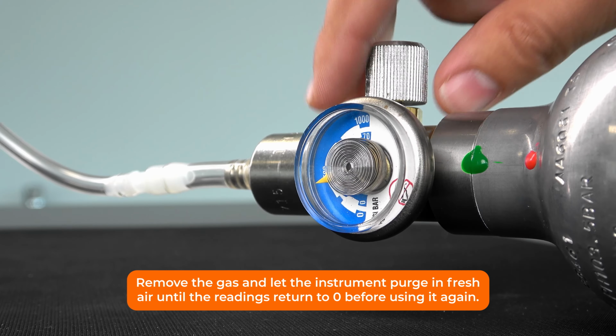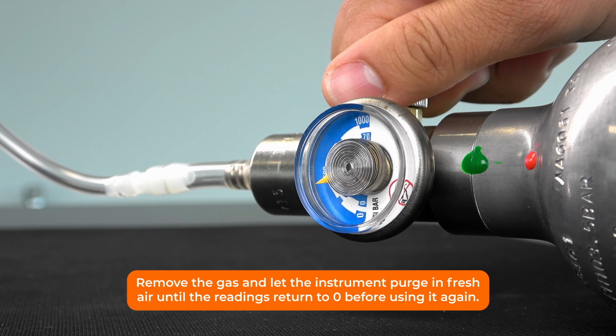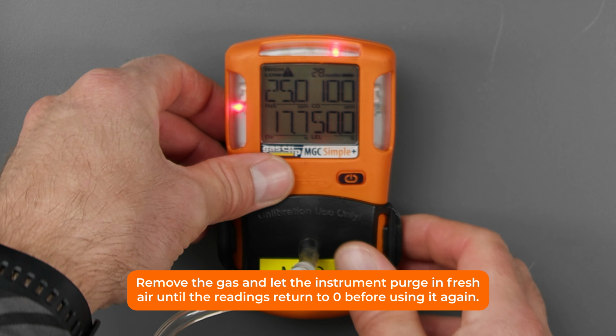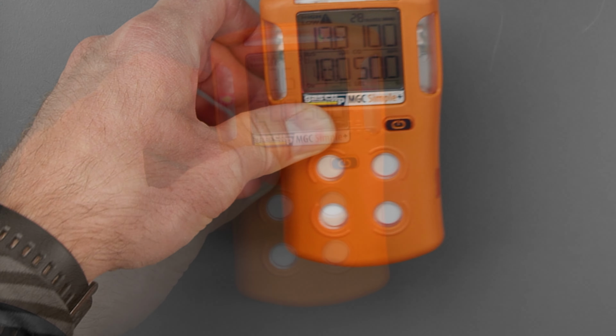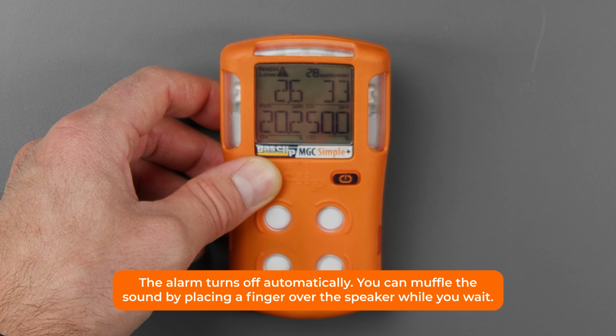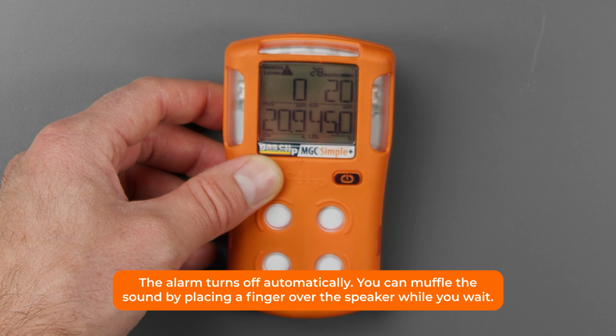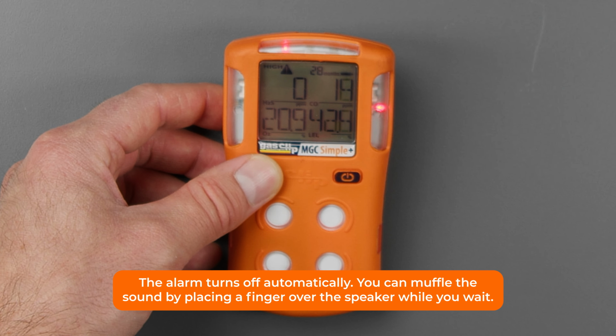Remove the gas and let the instrument purge in fresh air until the readings return to 0 before using it again. The alarm turns off automatically. You can muffle the sound by placing a finger over the speaker while you wait.